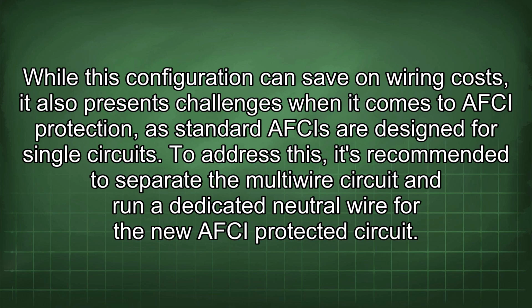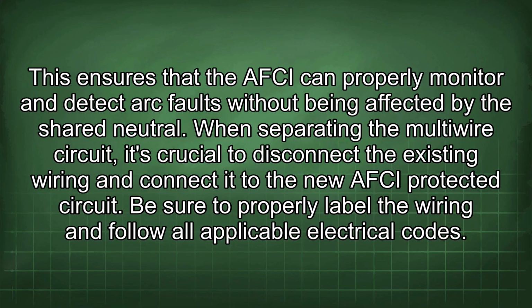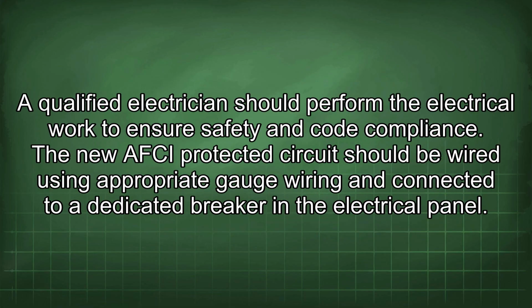To address this, it's recommended to separate the multi-wire circuit and run a dedicated neutral wire for the new AFCI protected circuit. This ensures that the AFCI can properly monitor and detect arc faults without being affected by the shared neutral. When separating the multi-wire circuit, it's crucial to disconnect the existing wiring and connect it to the new AFCI protected circuit. Be sure to properly label the wiring and follow all applicable electrical codes. A qualified electrician should perform the electrical work to ensure safety and code compliance.